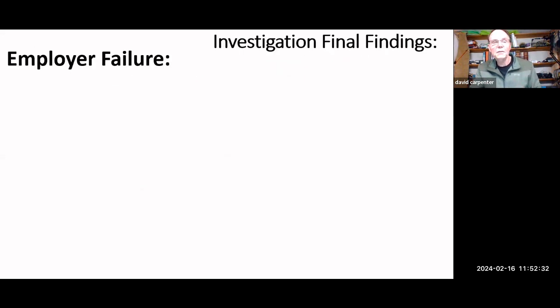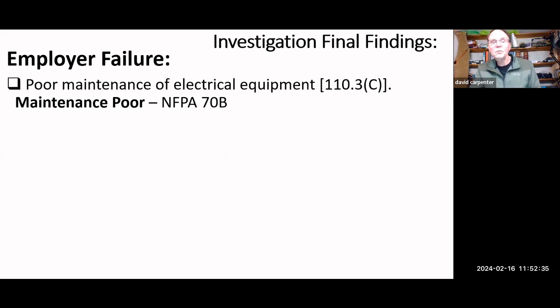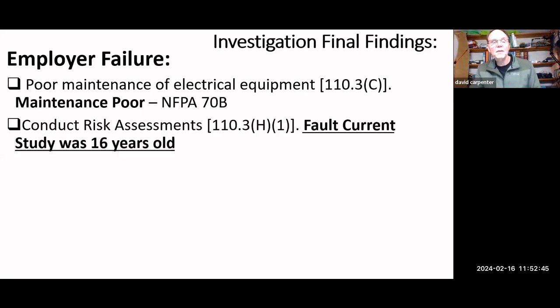These were the employer's failures: poor maintenance of the electrical equipment, which 110.3 requires, and NFPA 70B gives you guidance on how to maintain that equipment. They also found that they didn't conduct a risk assessment like they should have. 110.3(H)(1), found in NFPA 70E, is the standard they should follow. But they hadn't done an arc flash study on this plant in 16 years, even though you're required to do one every 5 years for the whole system.